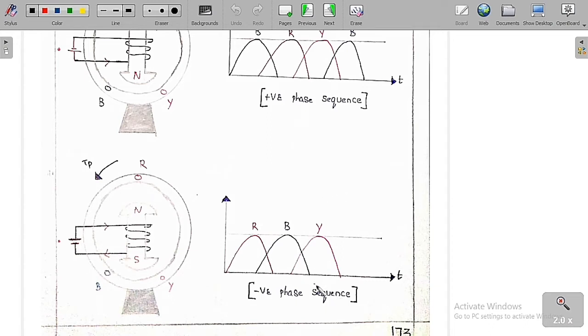So therefore we can say that if you want to change the phase sequence of the induced voltage in the stator winding, definitely you have to change the rotation of the shaft of the rotor, but not by interchanging the field winding supply voltage terminals. This is a very important point that you always have to understand. So the final conclusion is, if you want to change the phase sequence of the induced voltage in the stator coils, or simply the armature coils which are placed on the stator, you have to interchange the direction of rotation of the shaft of the rotor, and you don't have to change the remaining things.